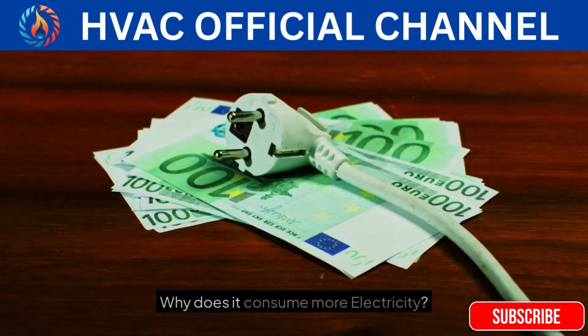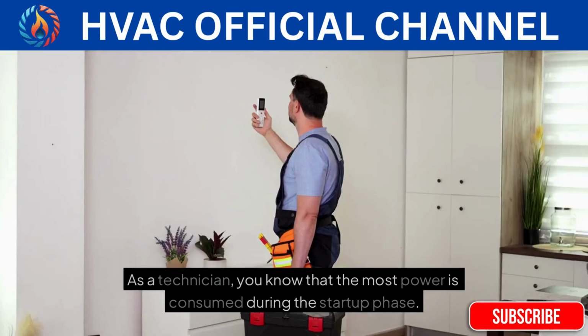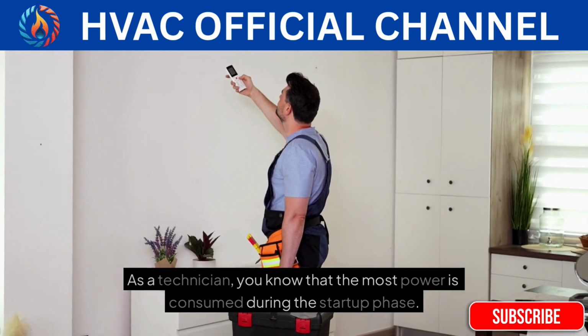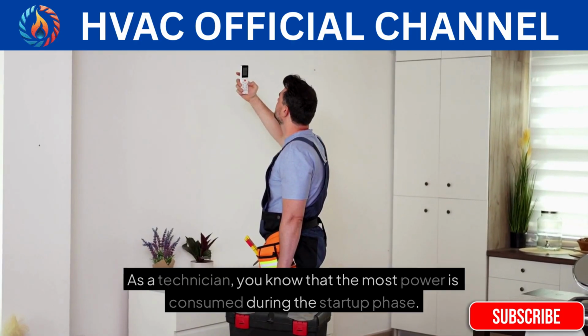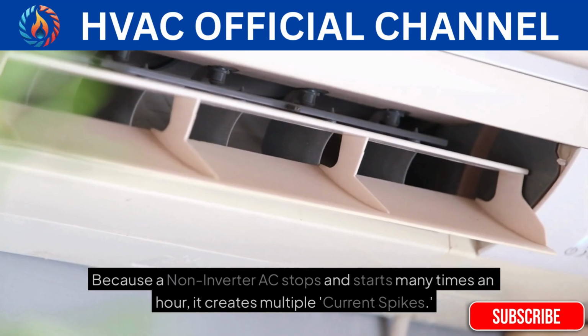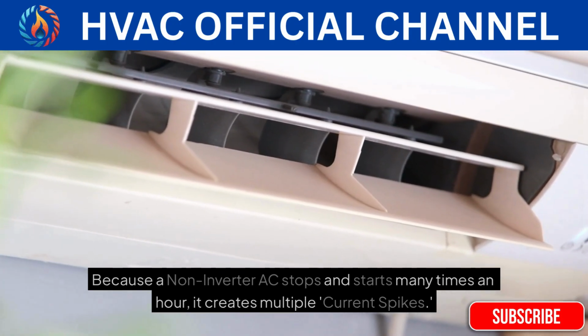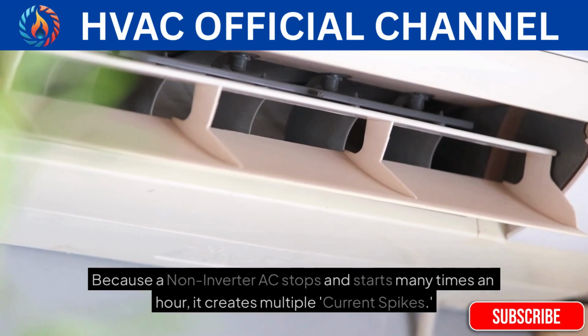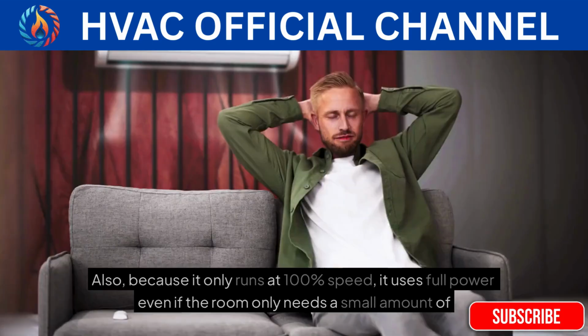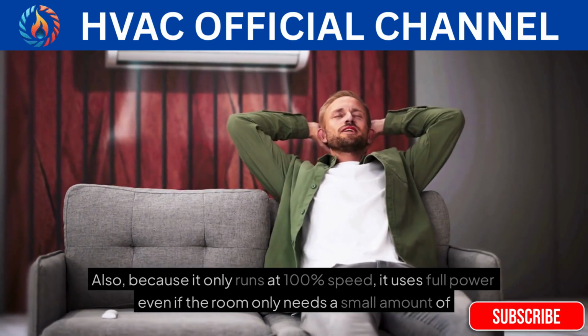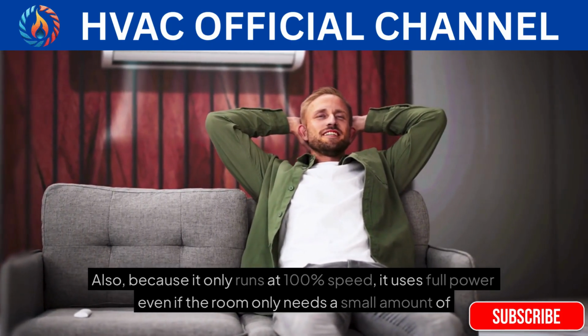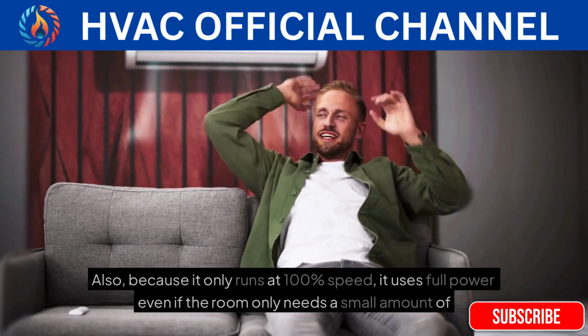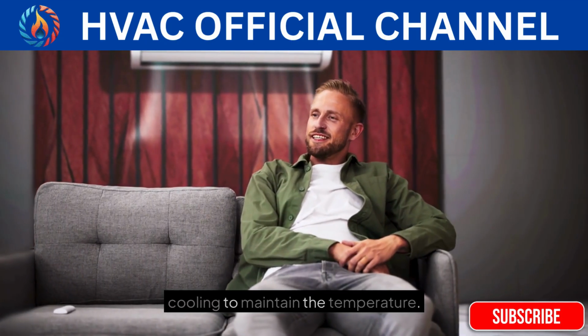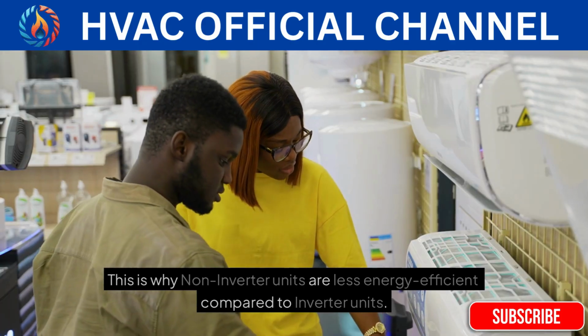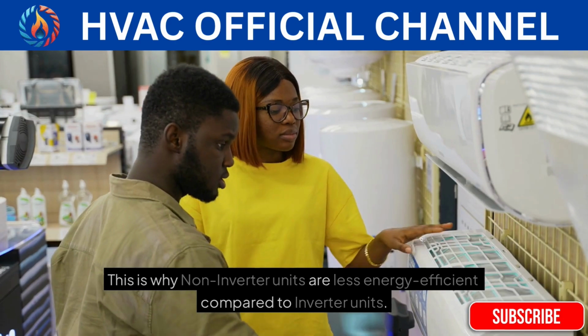Why does it consume more electricity? As a technician, you know that the most power is consumed during the startup phase. Because a non-inverter AC stops and starts many times an hour, it creates multiple current spikes. Also, because it only runs at 100% speed, it uses full power even if the room only needs a small amount of cooling to maintain the temperature. This is why non-inverter units are less energy efficient compared to inverter units.